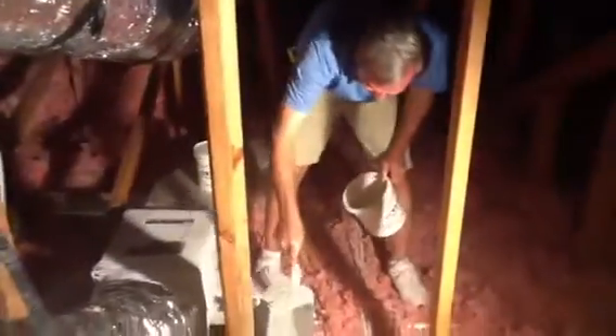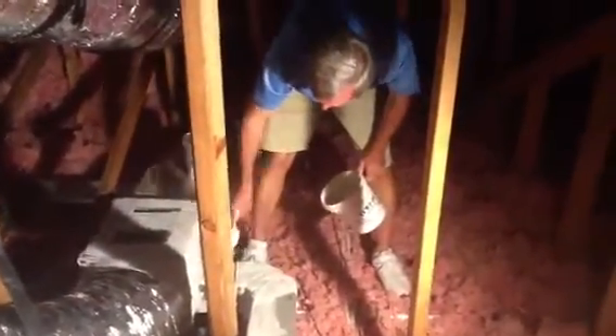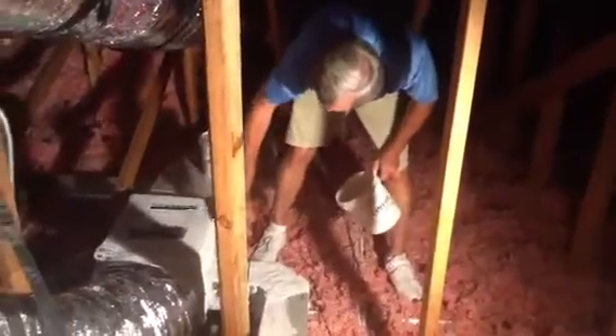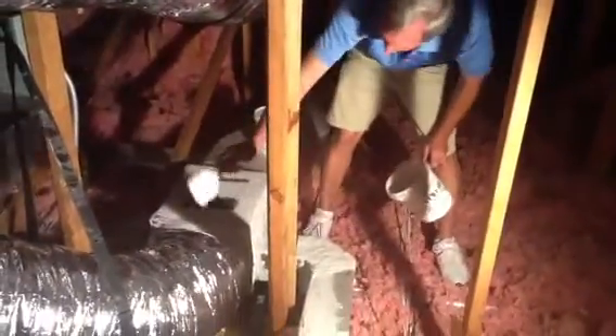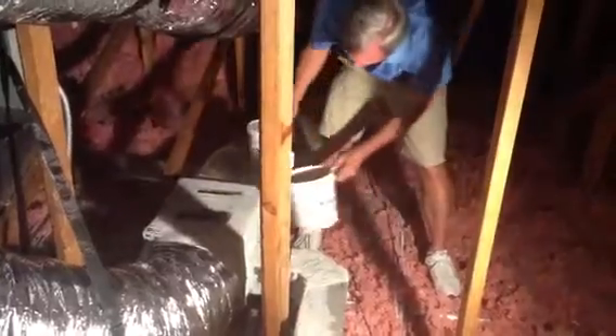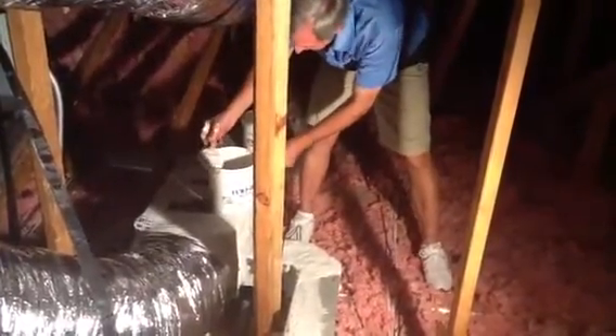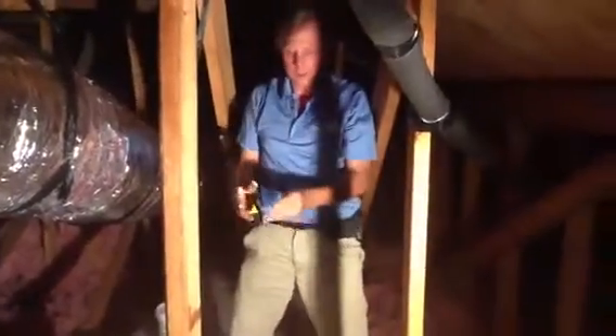So you get the general idea: any tape seams, any connection joints, any staples, any tape—everything has to be mastic and sealed. That includes flexible ductwork. What the code says is anything 30 inches or more.